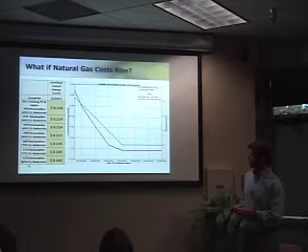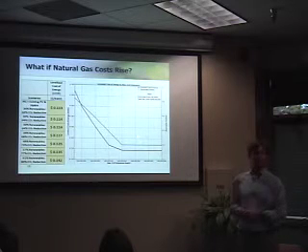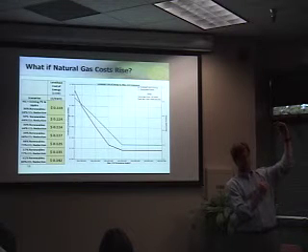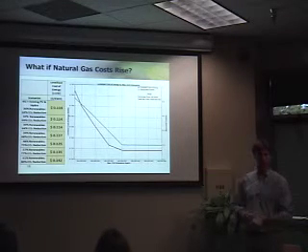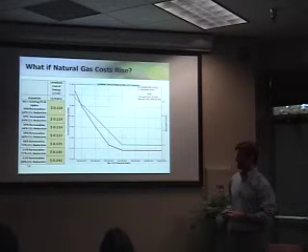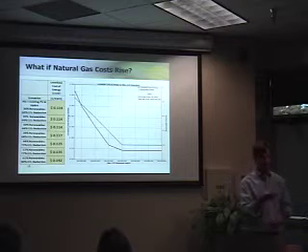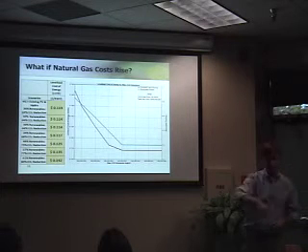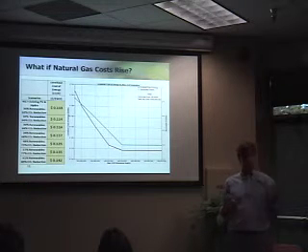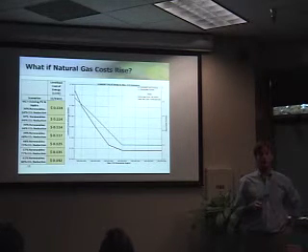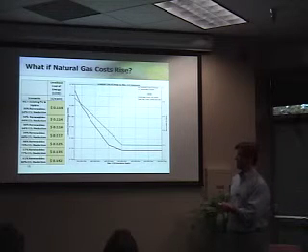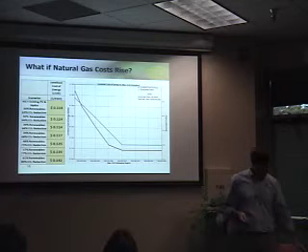What if natural gas costs rise? If we doubled natural gas costs, so it's at the complete top end of the highest price we've seen for the last 10 years, and it goes there, and we're stuck with our system, how much is it going to cost? It's going to cost 11.4 cents, including the 300 million upfront, including the 8 million. So we go from 8.4 up about 30-35% when we double our fuel costs. So everybody is afraid of this number. I don't think this is going to happen. I'm going to show you what the EIA thinks.